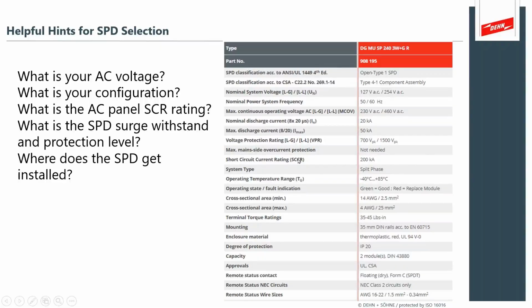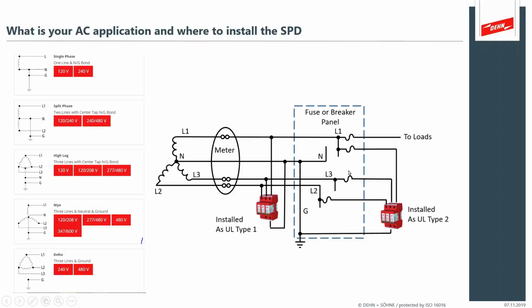So if you have a breaker upstream feeding your motor control center, you look at that breaker, it'll tell you it has a short circuit current rating, probably 200 kA, that's the highest sort of accepted rating. The SPD needs to match that rating or be disconnected from that breaker. So it's a really important aspect to match so it safely meets what the system can deliver as a fault. And then where does the SPD get installed? Does it get installed at the panel, or do you install it downstream directly off the motor or the variable speed drive?